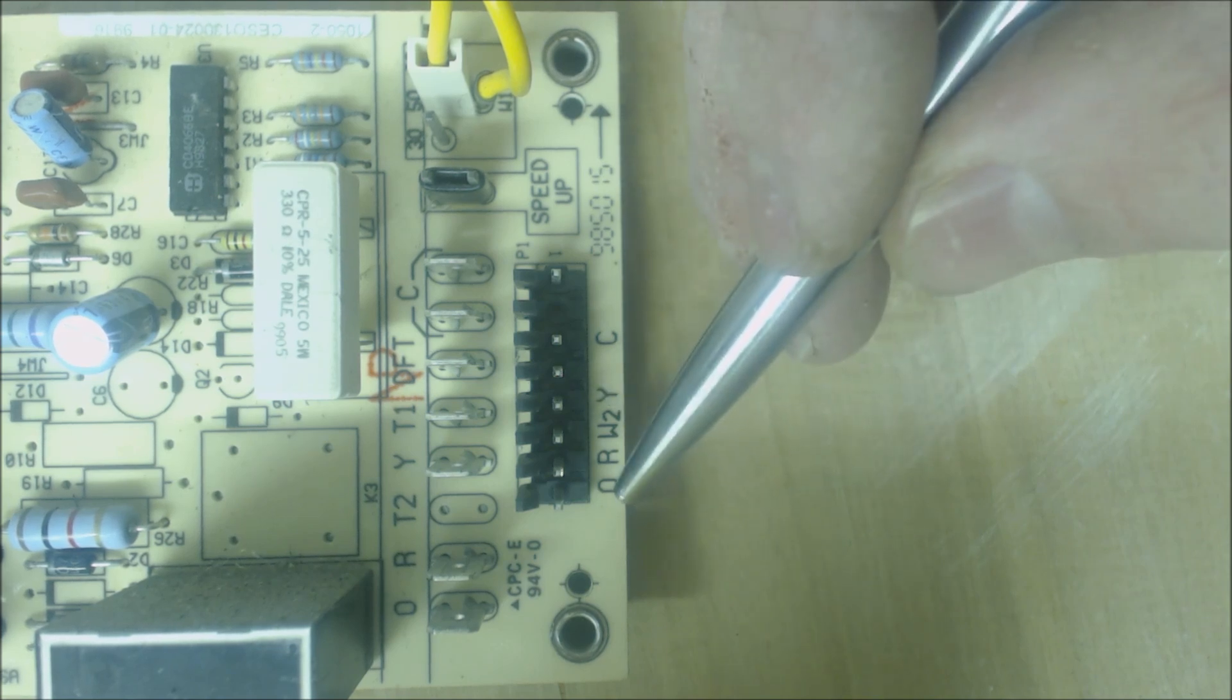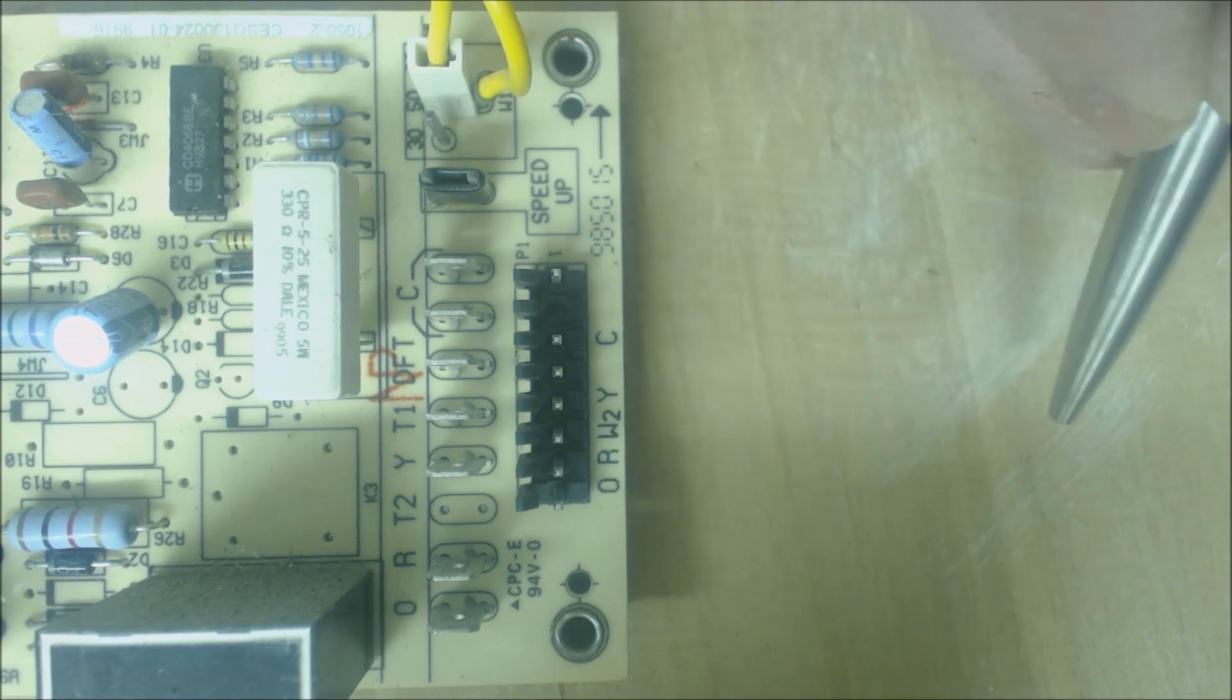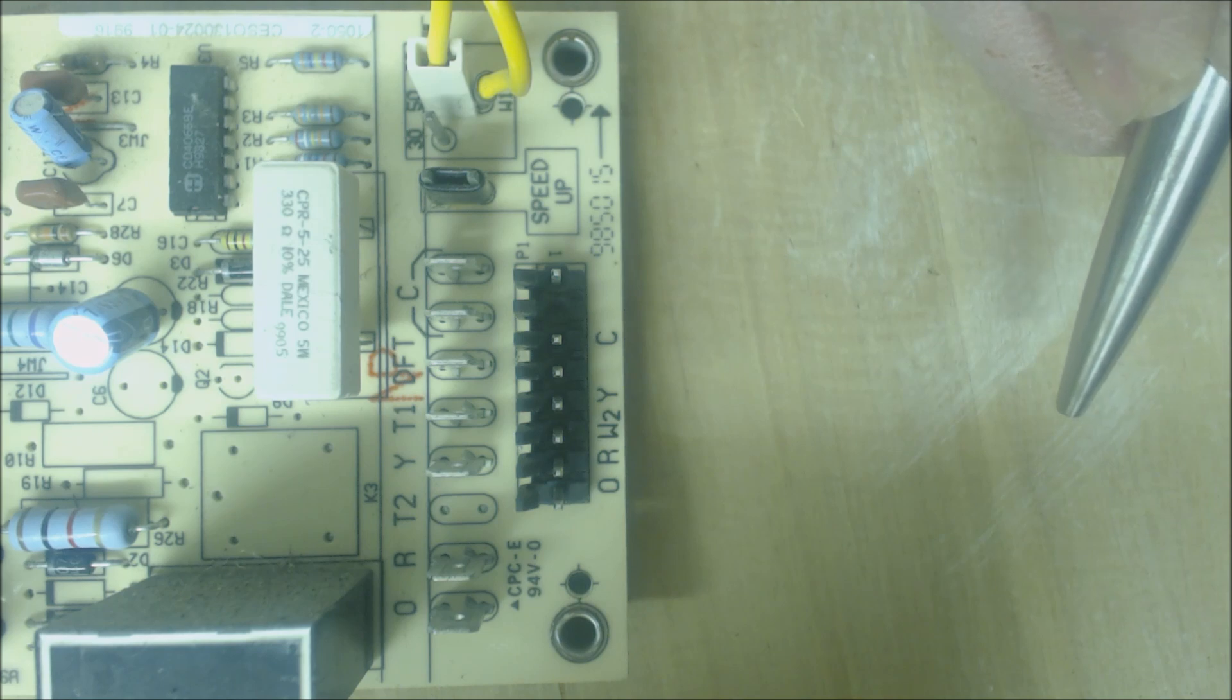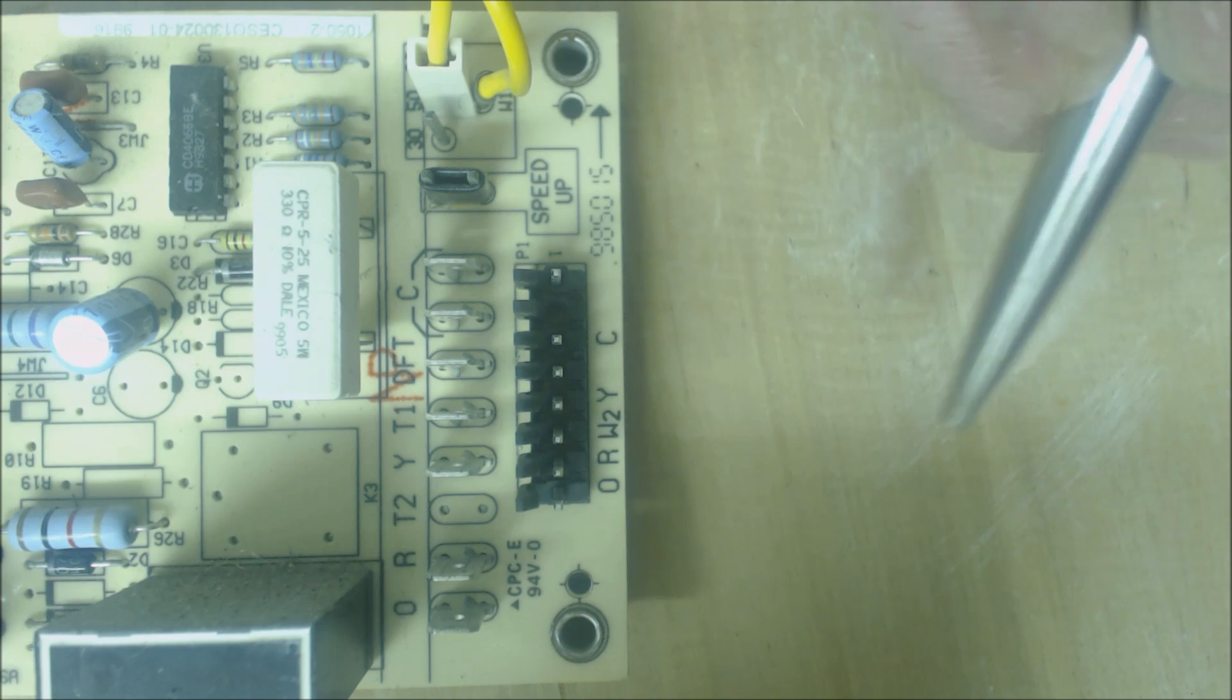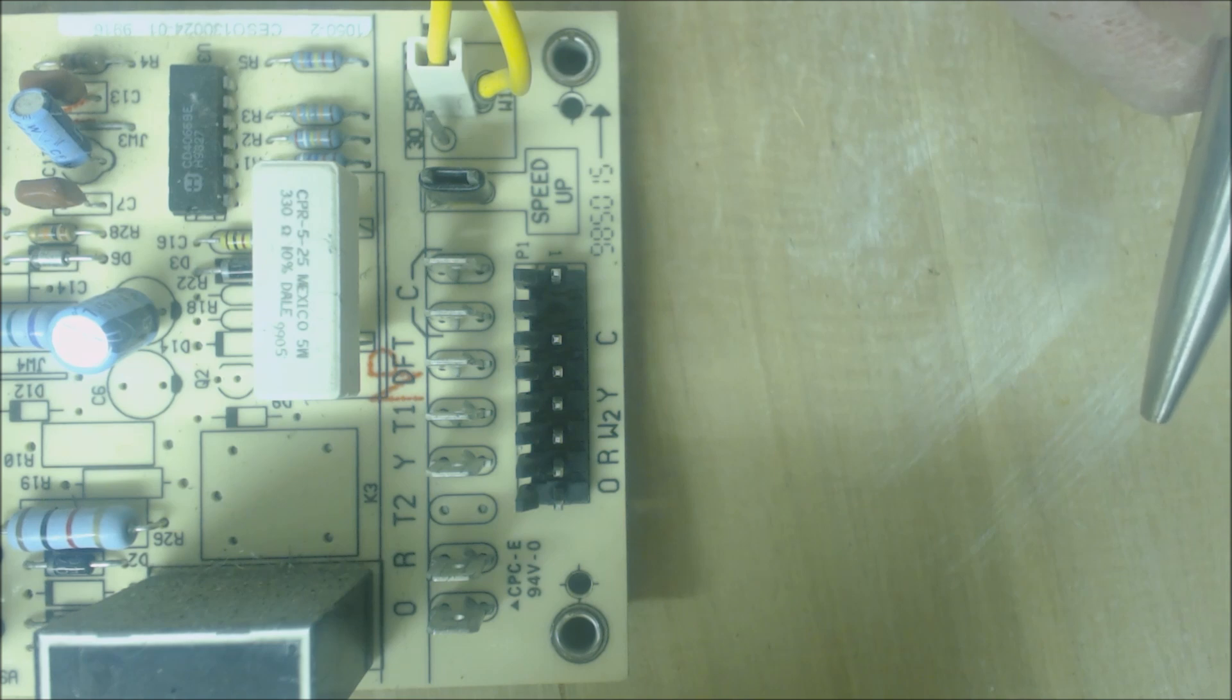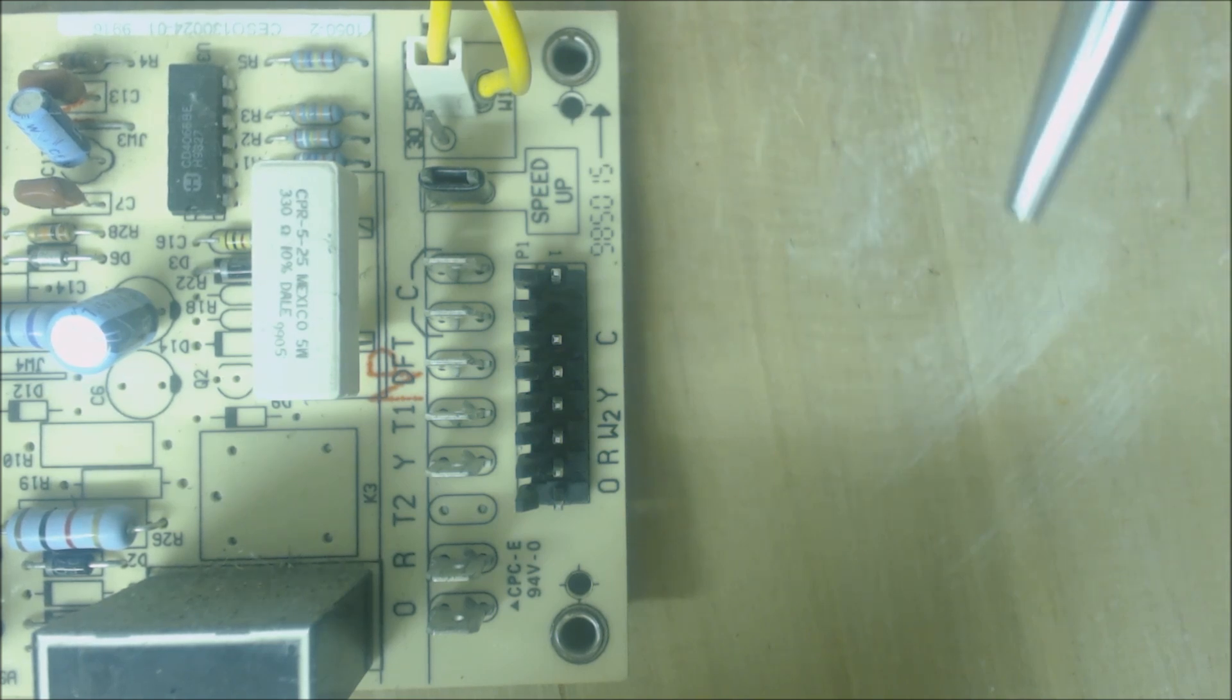O is 24 volt power coming in to power the reversing valve. On this unit, you're powering the reversing valve in cooling mode because this is a Carrier, Bryant, or Payne unit, not a Rheem. You power the reversing valve in cooling for most residential and commercial units other than Rheem or Ruud.